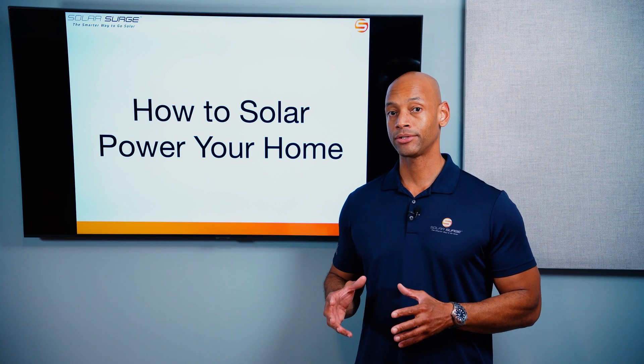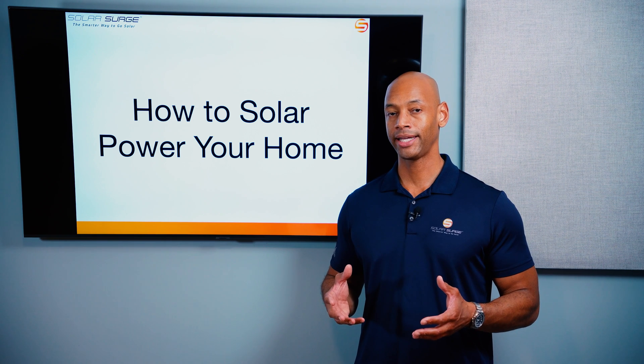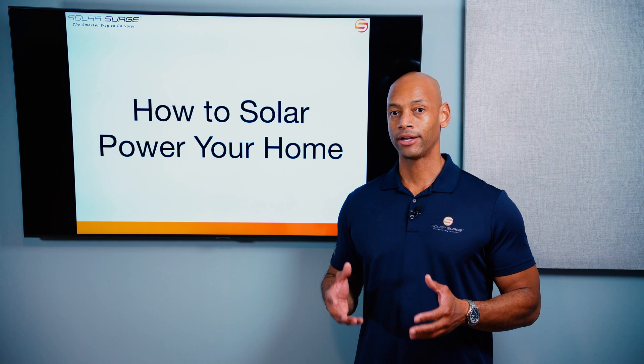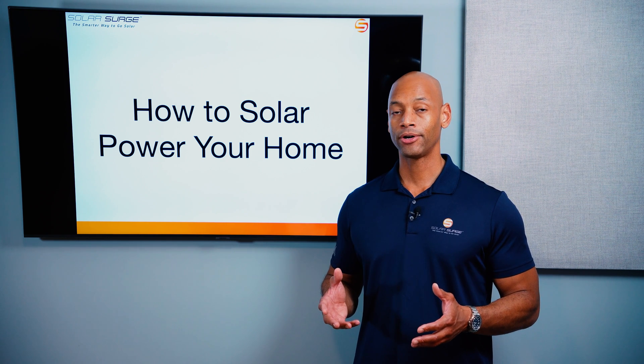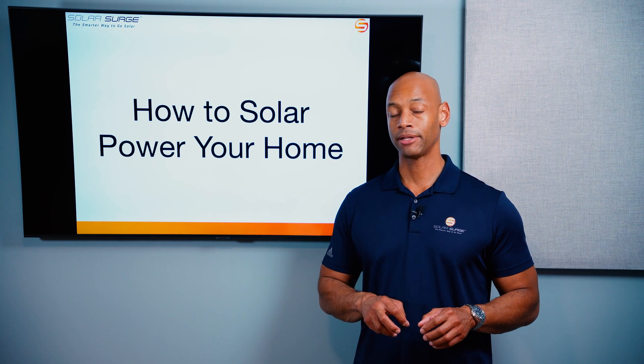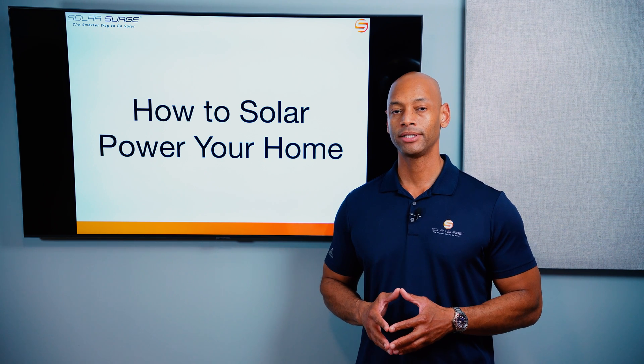With an off-grid solar power system, you have solar panels, battery storage, and in most cases an inverter as well. If you're setting up an off-grid cabin or lodge, you're typically going to want to wire it with 120-volt circuits like you have in your home. The inverter pulls direct current electricity off the solar panels and batteries and provides alternating current the same way you'd have in a normal grid-connected home. The off-grid system is great in places where you don't have access to utility power, or if you want to use it as an emergency backup power source.